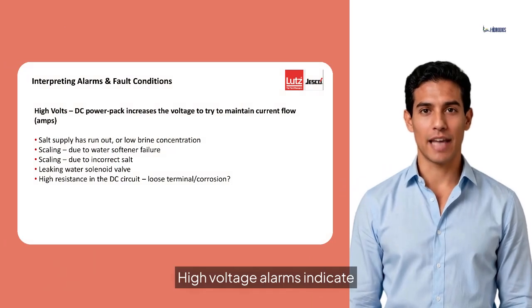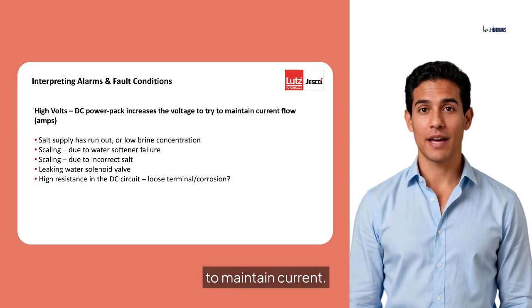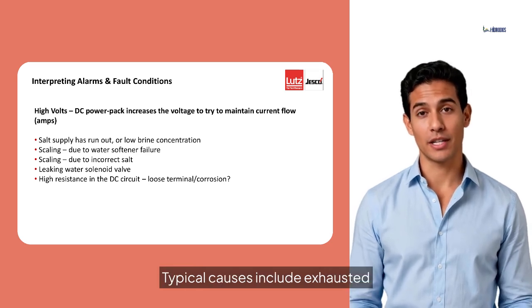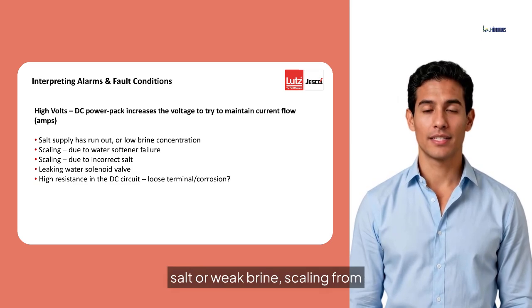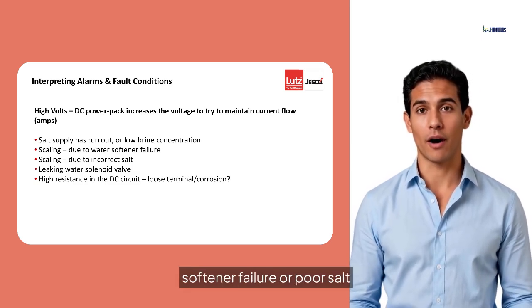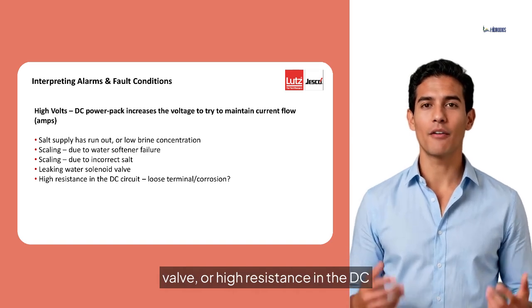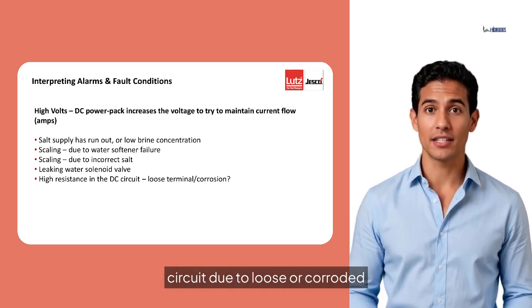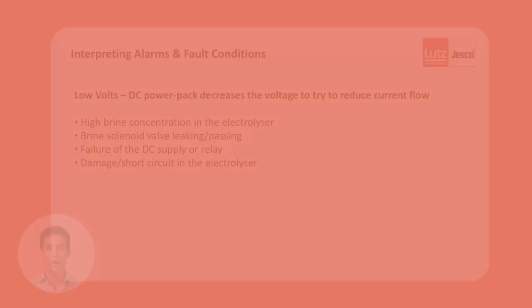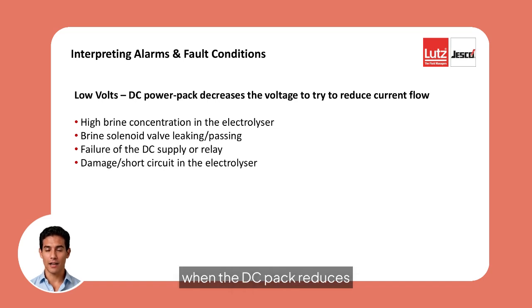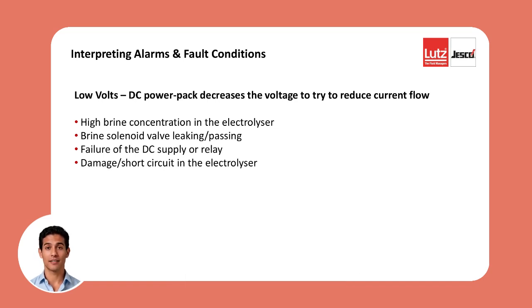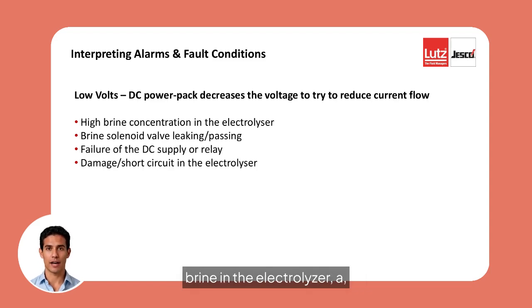High voltage alarms indicate the DC pack is increasing voltage to maintain current. Typical causes include exhausted salt or weak brine, scaling from softener failure or poor salt quality, a leaking water solenoid valve, or high resistance in the DC circuit due to loose or corroded terminals. Low voltage alarms occur when the DC pack reduces voltage to limit current. Likely causes are overly strong brine in the electrolyzer, a leaking brine solenoid valve, failure of the DC supply or relay, or internal damage or short circuit within the electrolyzer cell assembly.